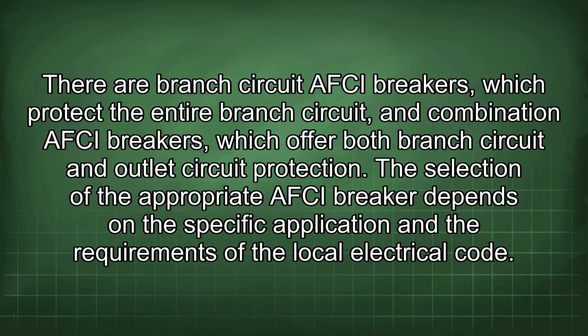Understanding the different types of AFCI breakers is also essential. There are branch circuit AFCI breakers, which protect the entire branch circuit, and combination AFCI breakers, which offer both branch circuit and outlet circuit protection. The selection of the appropriate AFCI breaker depends on the specific application and the requirements of the local electrical code.